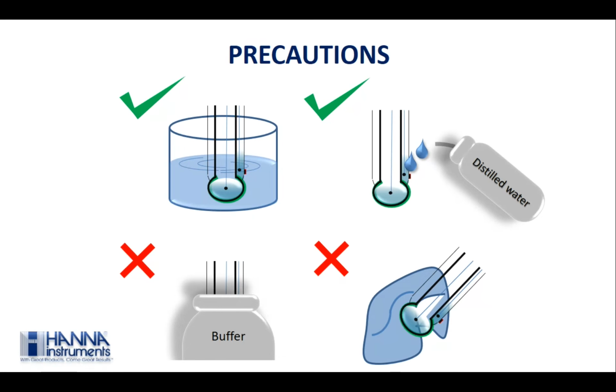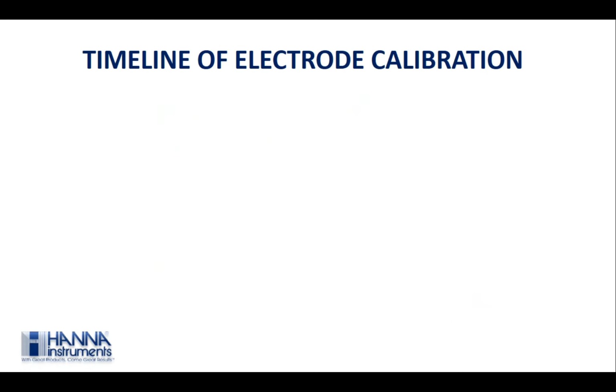People many times ask when you should calibrate the meter or what the frequency of calibration should be. One thing everyone should understand is that we calibrate the electrode and not the meter. The meter has all the algorithms set in its circuit, and the calibration of the electrode is necessary as the electrode is a mechanical part that senses the activity in terms of millivolts, and then these readings are converted into pH readings.